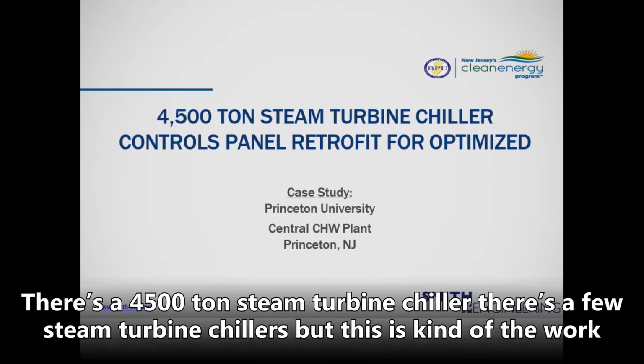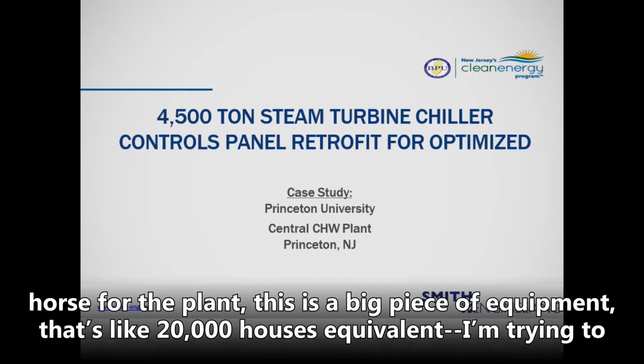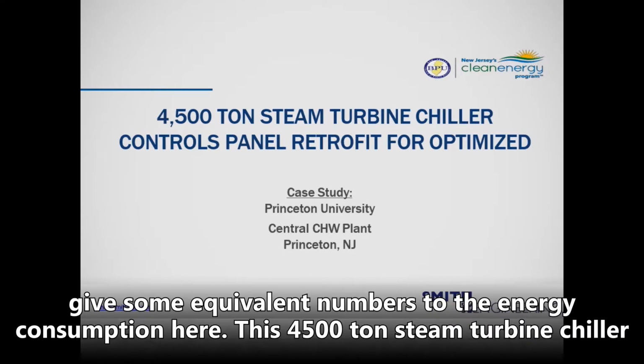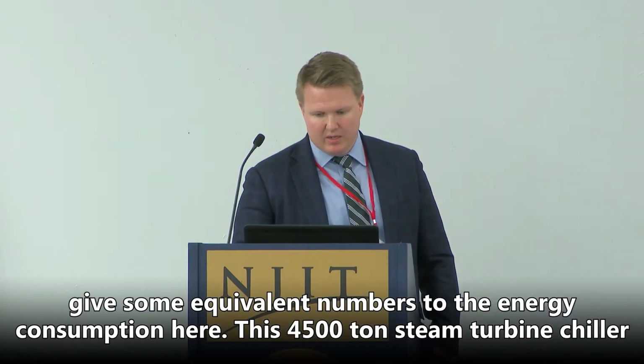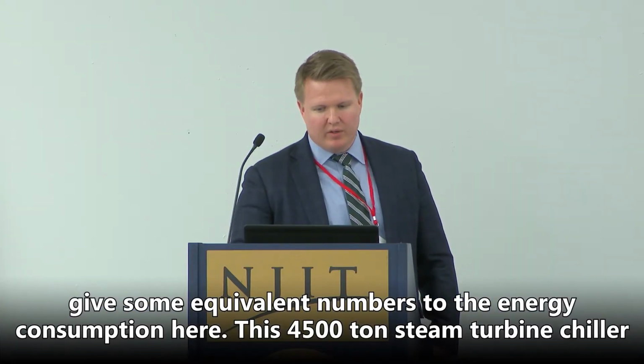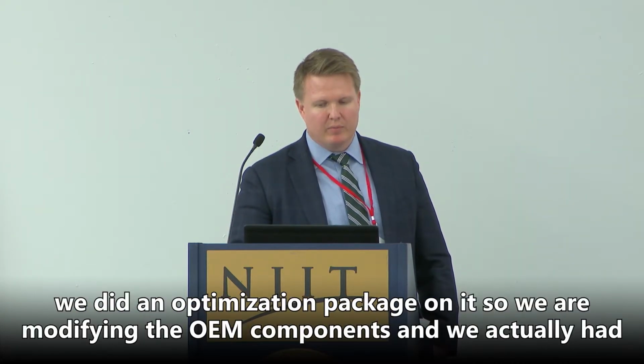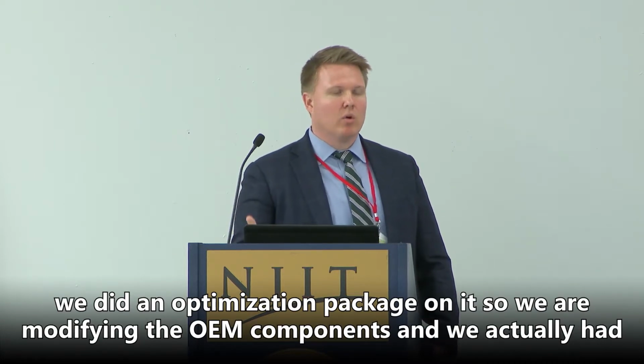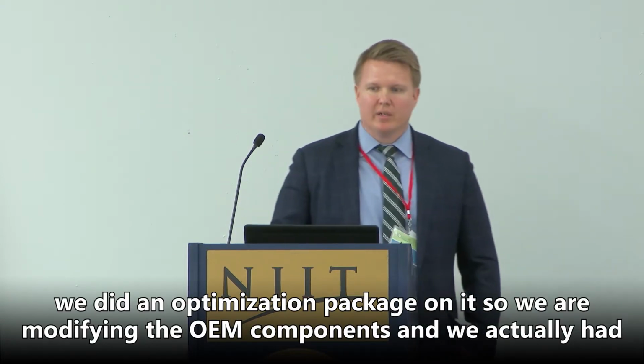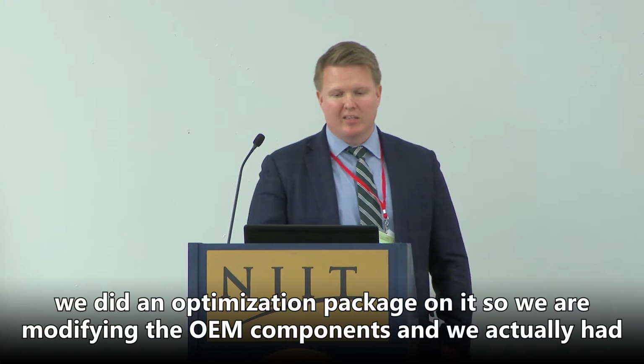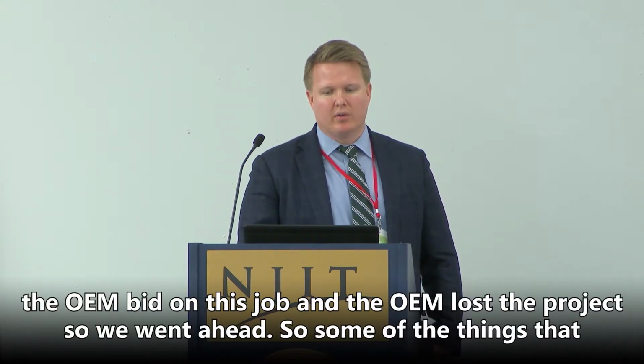So there's a 4,500 ton steam turbine chiller. There's a few steam turbine chillers, but this is kind of the workhorse for the plant. So there's a big piece of equipment that's like 20,000 houses equivalent. I'm trying to give some equivalent numbers to the energy consumption here. This 4,500 ton steam turbine chiller, we did an optimization package on it.